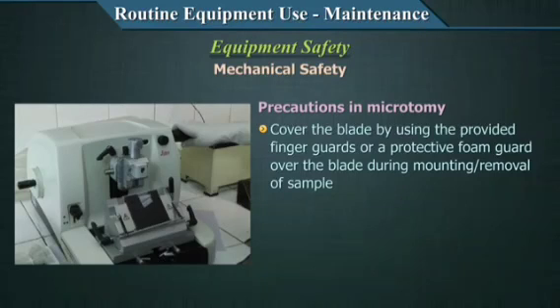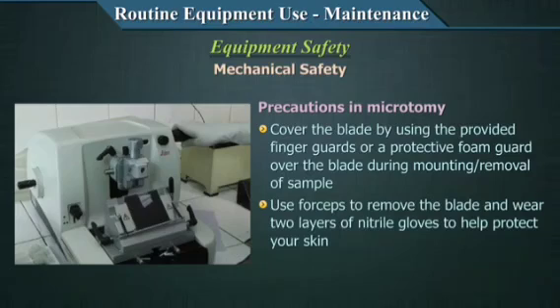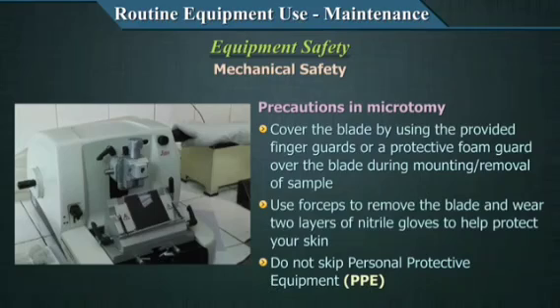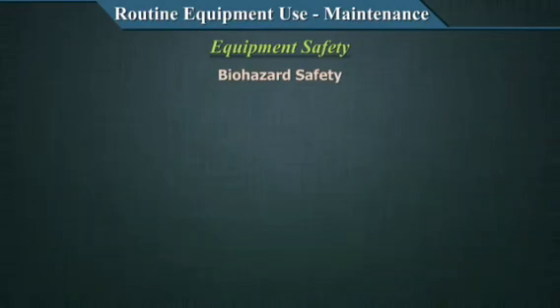Cover the blade by using the provided finger guards or a protective foam guard over the blade during mounting and removal of the sample. Use forceps to remove the blade and wear two layers of nitrile gloves to help protect your fingers as far as possible. You do that. Final big warning: do not skip personal protective equipment while using microtomes. This will prevent lacerations and cuts. So now we talked about two kinds of safety where equipment is concerned, electrical and mechanical. Let's go to the third, which is biohazard and biosafety.